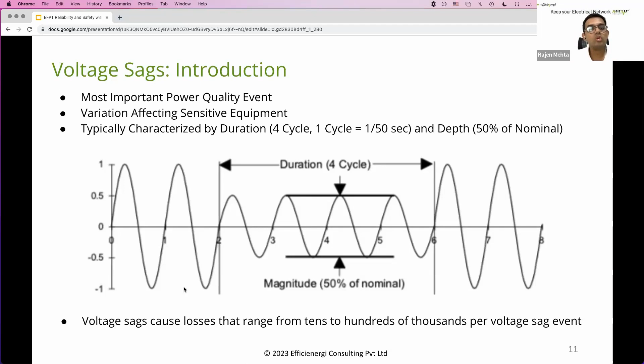So what is the impact of these voltage sags on certain nonlinear equipment? Very quickly, I take the example of a drive. The drive trips on undervoltage. Why does it trip? Because the utility supply voltage goes down during a voltage sag, and thus the DC link voltage, which transfers the voltage to the inverter, is low. At the inverter, you will have a low DC bus voltage too.